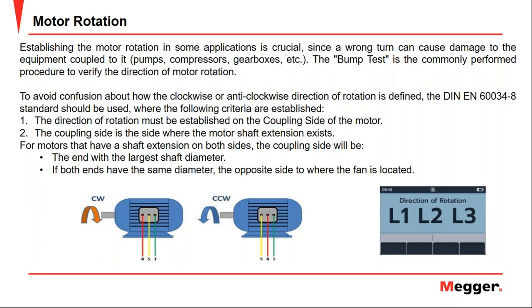Well, the standard DIN EN 60034-8 helps us clarify doubts and define the direction of rotation depending on the system configuration, as we can see here. The direction of rotation must be established on the coupled side of the motor. So the first thing we have to do is identify the coupling side of the motor. The coupling side is the side where the motor shaft extension exists.